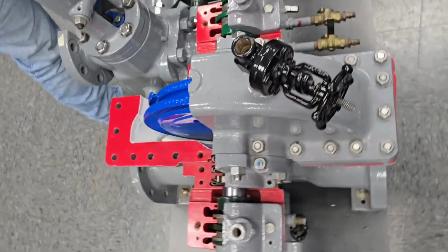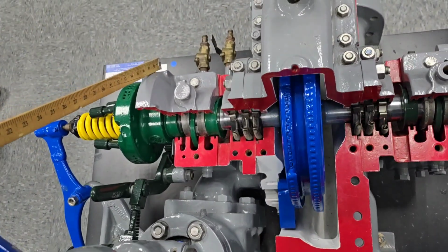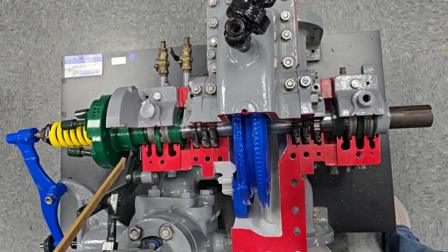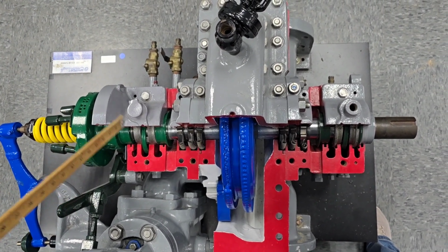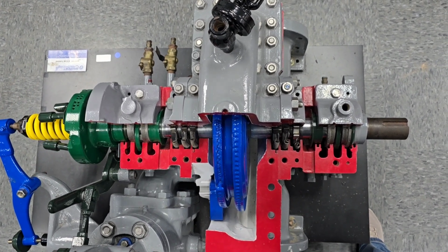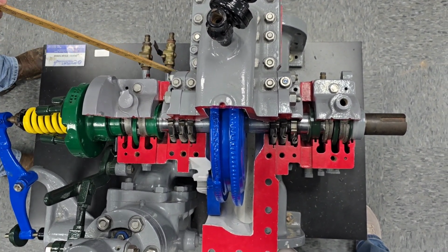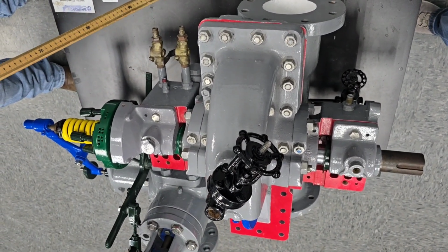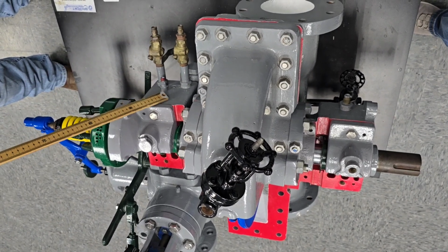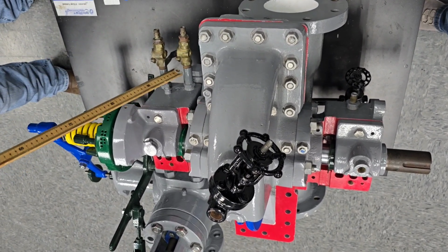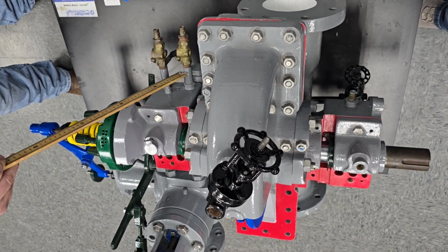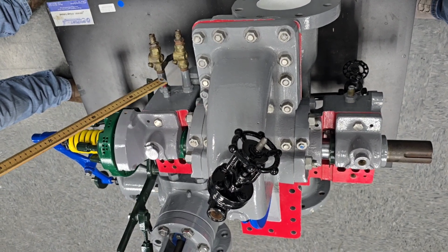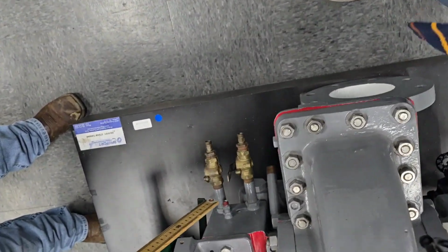Past the governor, we have an outboard bearing housing. This bearing housing is going to hold the lubrication for your bearings. As an operator, you need to be aware of the temperature of your bearing, of your lubrication, which is going to have ports on this side. This is going to allow for cooling water to enter into the bearing housing, transfer heat, and to be removed. There should always be a difference in temperature on your cooling water in versus your cooling water out. If they're ever the same, that would indicate an issue, and that would most likely be a cause of a blockage.